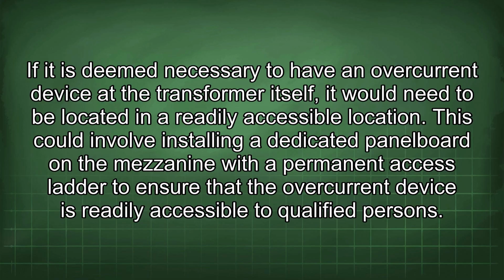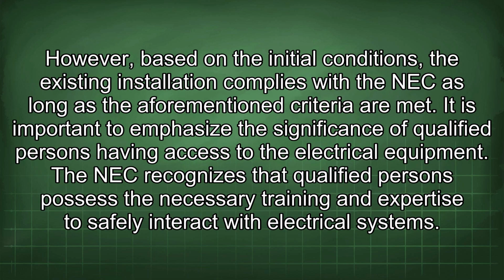This could involve installing a dedicated panel board in the mezzanine with a permanent access ladder to ensure that the overcurrent device is readily accessible to qualified persons. However, based on the initial conditions, the existing installation complies with the NEC as long as the aforementioned criteria are met. It is important to emphasize the significance of qualified persons having access to the electrical equipment.